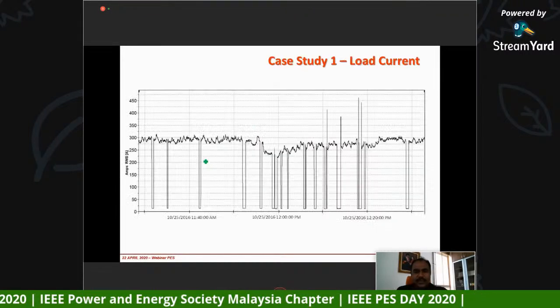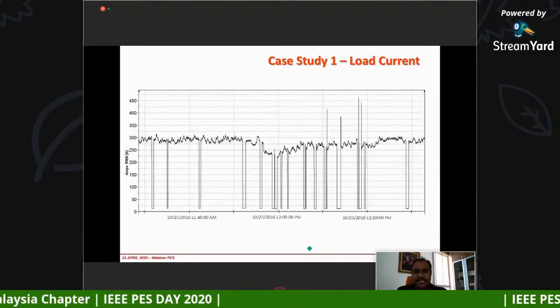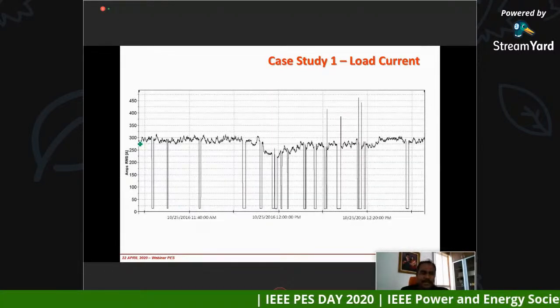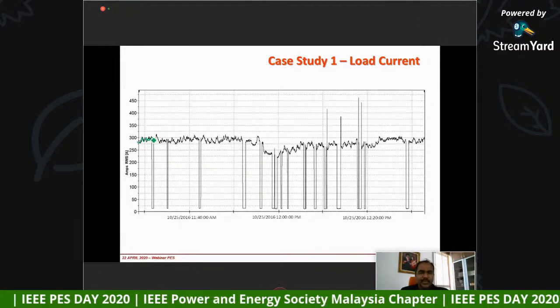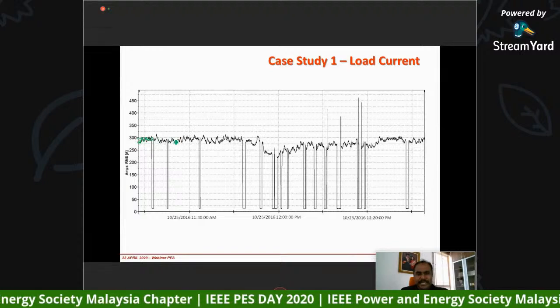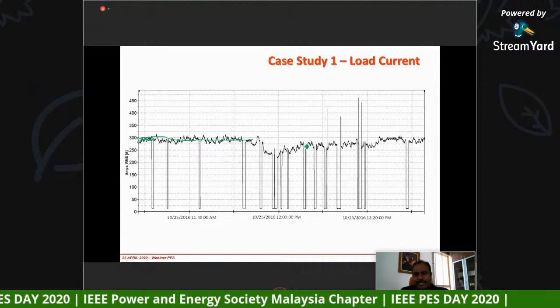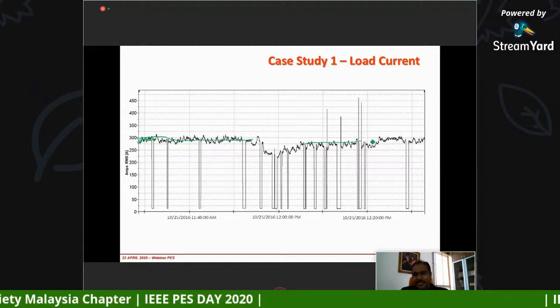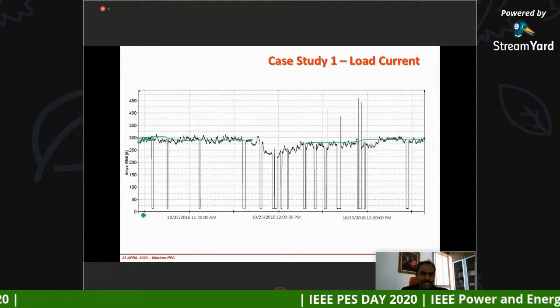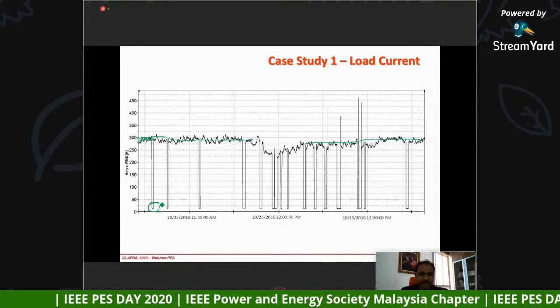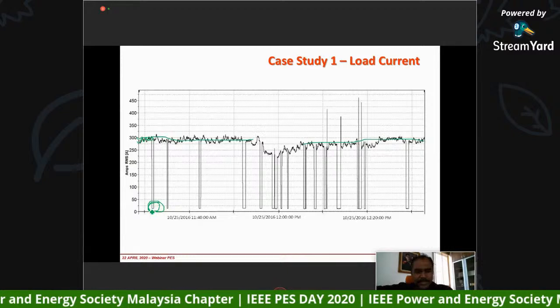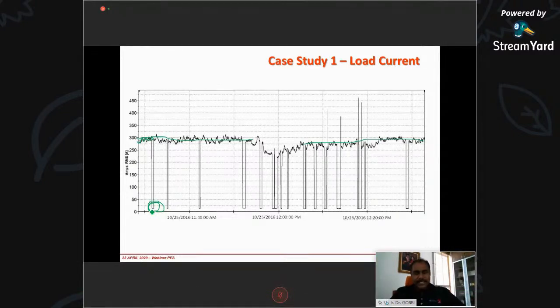Now, we actually measured the current for this particular system. If you notice, it is drawing approximately 290 amps. Sometimes it drops, but it's always above 200. Sometimes you notice that it drops to about 14 or 15 amps. Why does it drop? Because when they see some issue with the product, they automatically give an instruction for the clutch to disengage. Then the motor will be running without load, and we see the current drop to about 14 amps. But when the clutch is engaged again, it shoots up to more or less 290 amps.